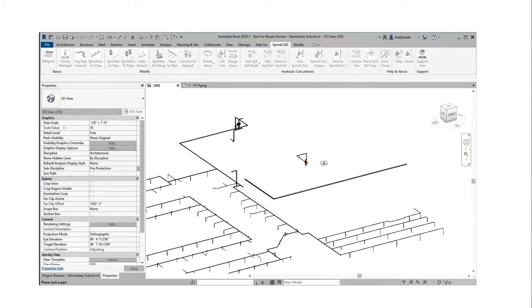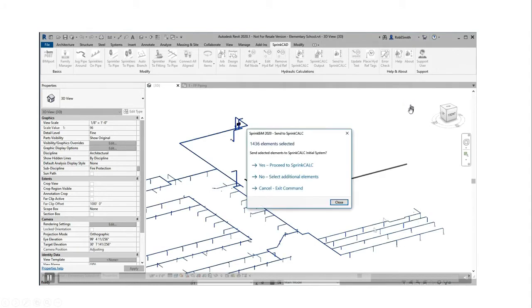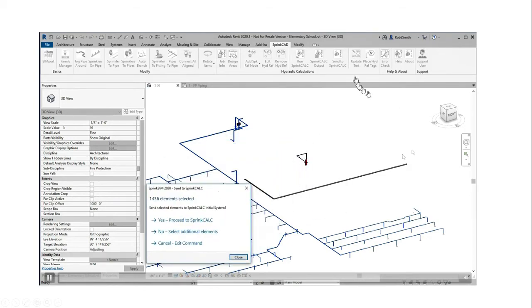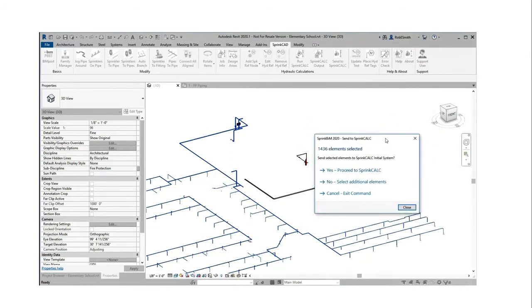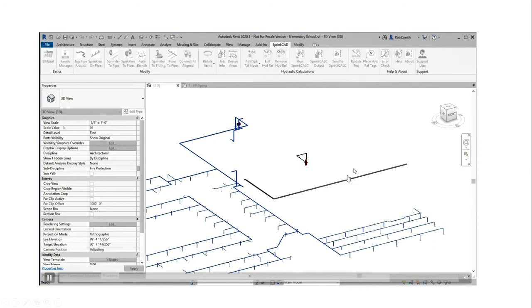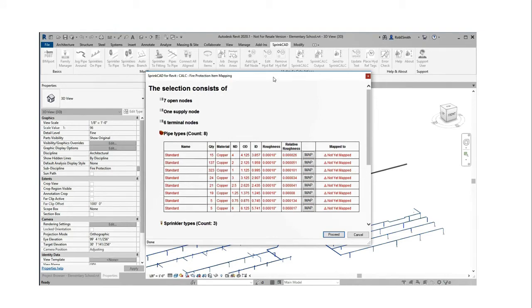Now I'm about to run this calc. When I click run calc, the program asks me to pick a pipe — any pipe in the system. Some pipe out here is not in the system; it was part of a future extension. I pick any piece of pipe that runs between the design area and the riser, and that piping all goes blue. I get the option to say yes, run the calc, or no, there's more pipe to connect, or cancel. It needs to be a completed, connected system. If you have disjointed pieces, you can use the 'send to SprinkCALC' option to fill in the blanks within our calc environment.